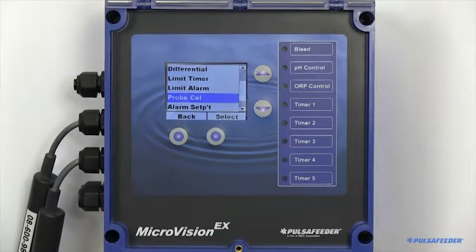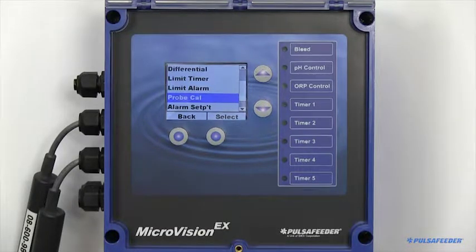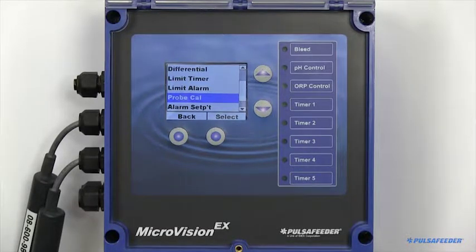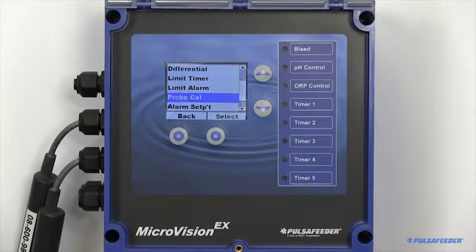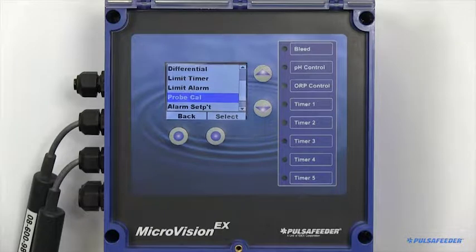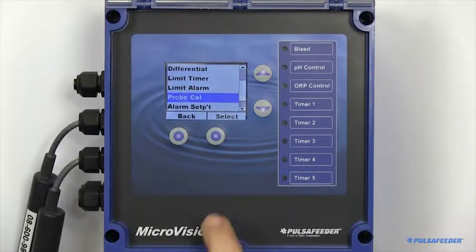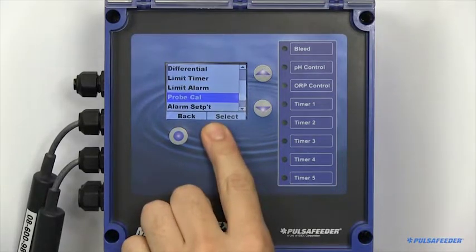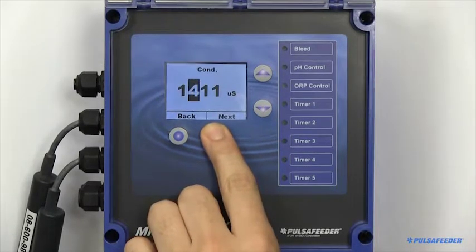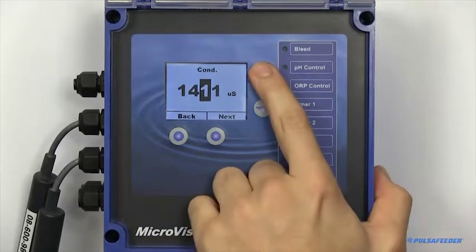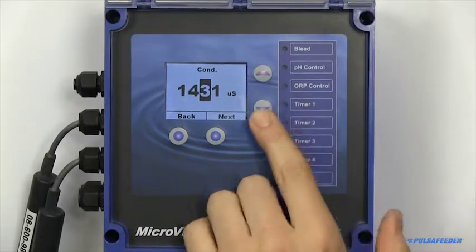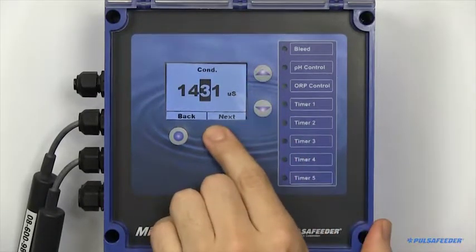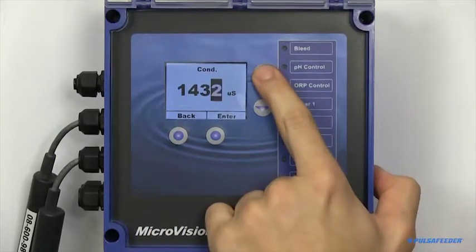Calibration of your probes is also essential. Some things to remember is that temperature fluctuations can affect some readings. Make sure the probes are in the desired solution for a minimum of 10 minutes. If using a handheld to calibrate, also make sure the handheld has temperature compensation.